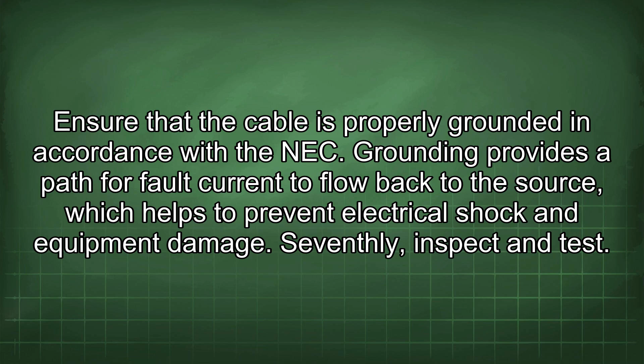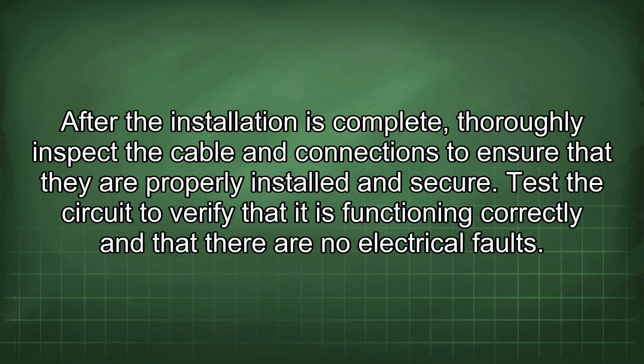Seventhly, inspect and test. After the installation is complete, thoroughly inspect the cable and connections to ensure that they are properly installed and secure. Test the circuit to verify that it is functioning correctly and that there are no electrical faults. Understanding the different types of cables recognized by the NEC can also help in selecting the appropriate cable for an installation, even if SER cable isn't specifically mentioned.